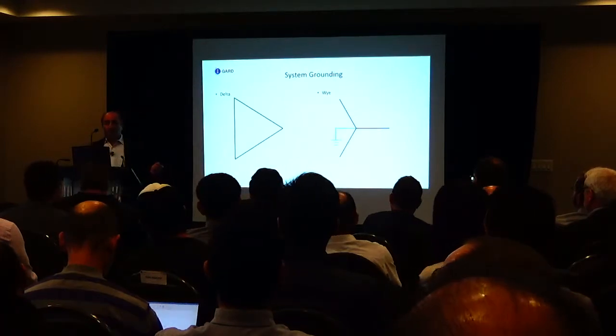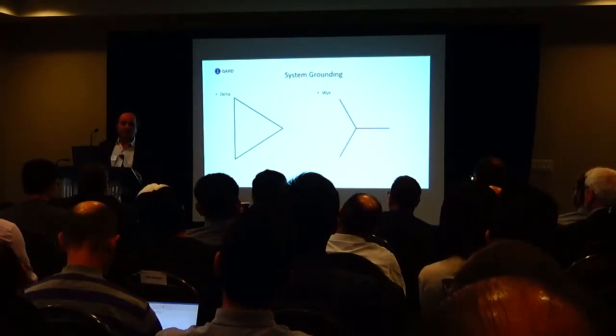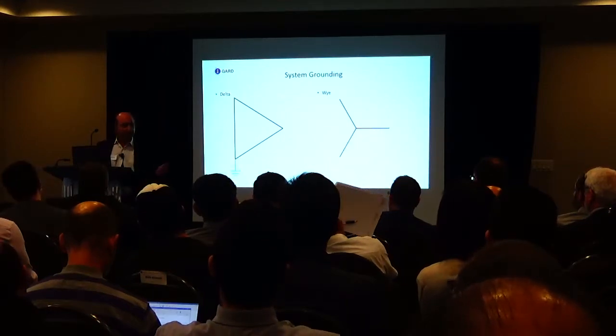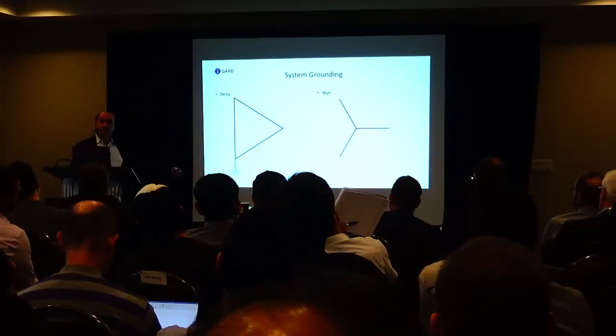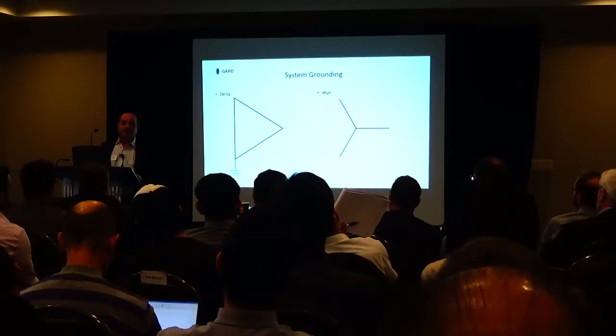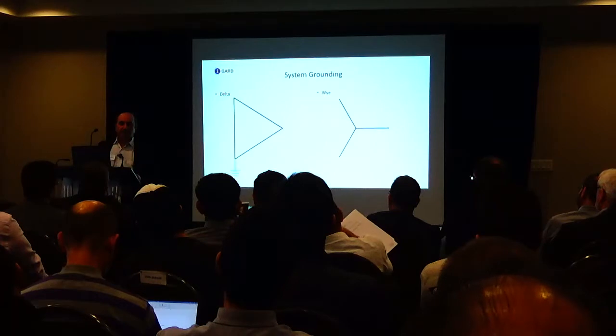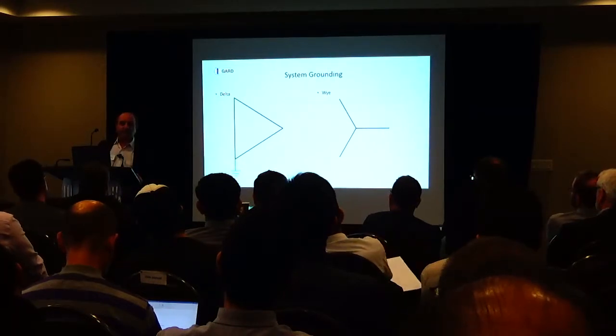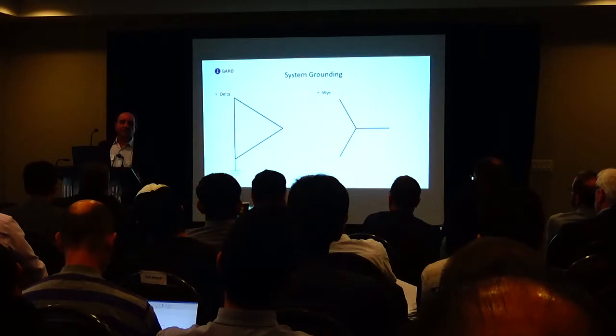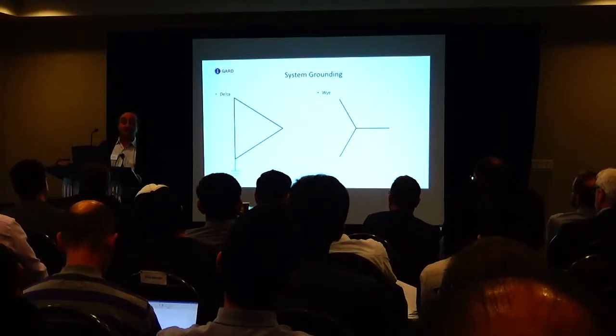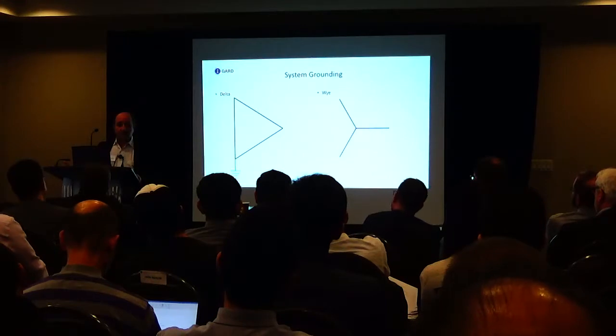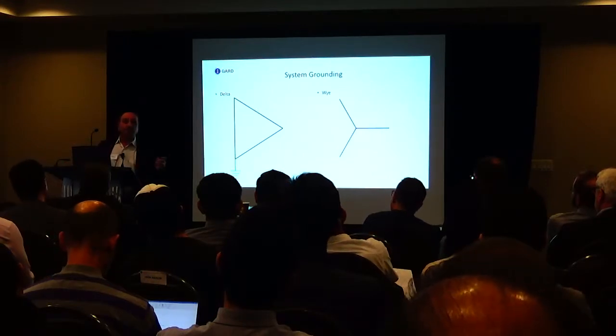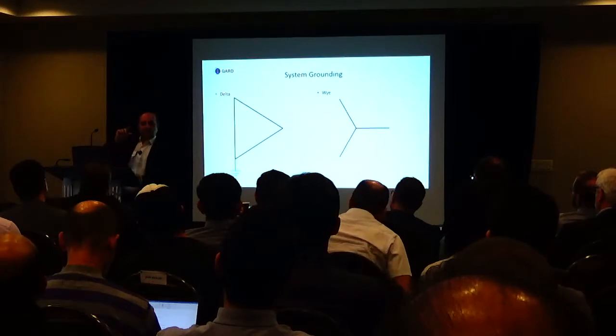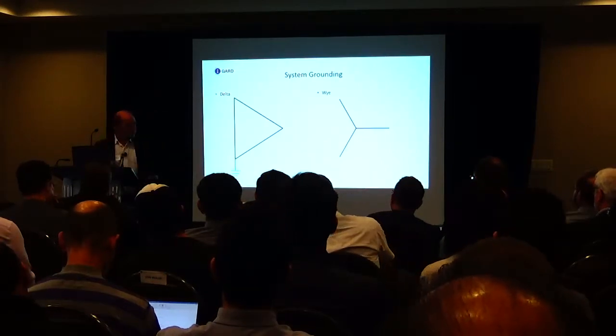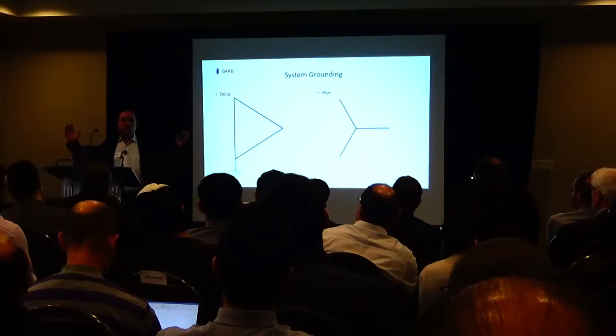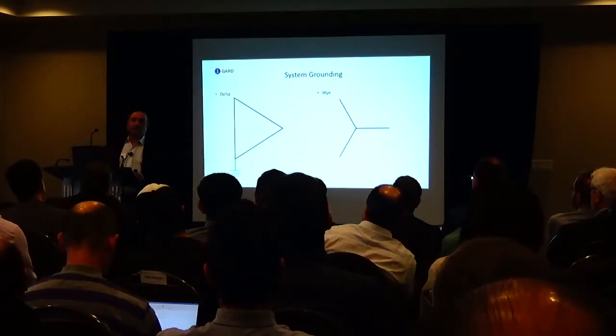When you have a fault on your system, haven't you just converted your system to this? So now you have a solidly grounded system. It's functioning as a solidly grounded system. So we went from a resistance grounded system to a solidly grounded system, and now different rules apply. So yes, you have to do something before something else happens. And this is where I think the qualified person is meant. The qualified person needs to look at this and say, okay, now my system has changed. What do I need to look at now?